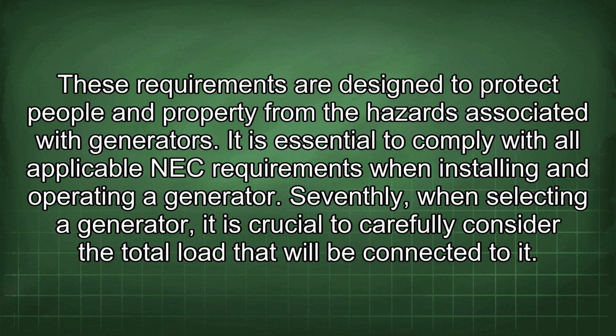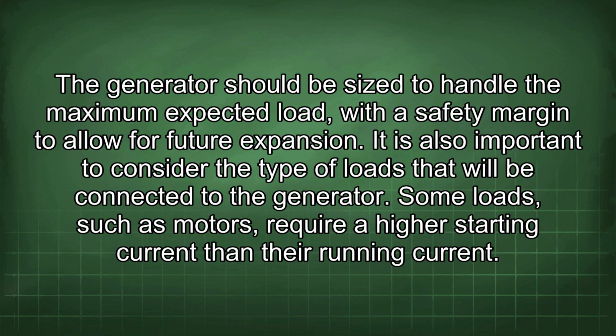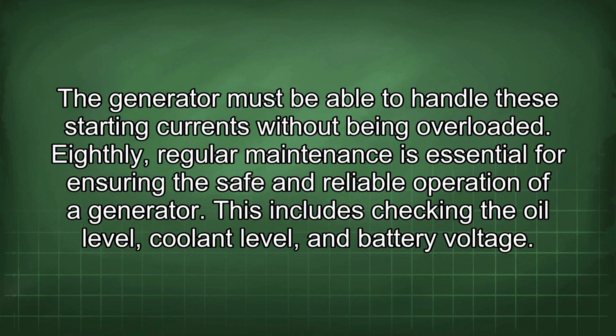Seventhly, when selecting a generator, it is crucial to carefully consider the total load that will be connected to it. The generator should be sized to handle the maximum expected load, with a safety margin to allow for future expansion. It is also important to consider the type of loads that will be connected to the generator. Some loads, such as motors, require a higher starting current than the running current. The generator must be able to handle these starting currents without being overloaded.